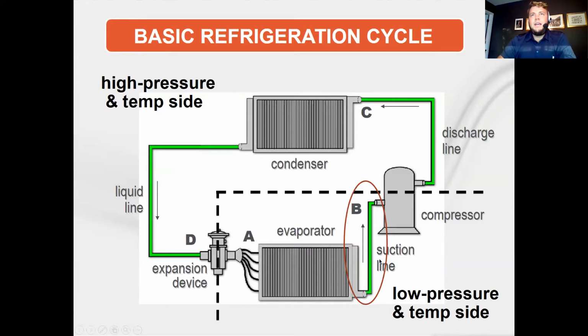So as we go through this slide deck, the biggest components that we're focusing on here are right here in our suction line. We want to ensure that it is sized properly, in hopes of making sure the oil that's inherent in a refrigeration system, which is used to lubricate the compressor, makes its way through the system and back to the compressor where it's needed the most. So it's a critical spot here in the suction line. And then elsewhere, we have a focus on oil, energy efficiency, and minimizing the refrigerant volume of the entire system itself. Those are our main goals as we focus going forward. So I will turn it back over to Mike to talk about some industry knowledge.